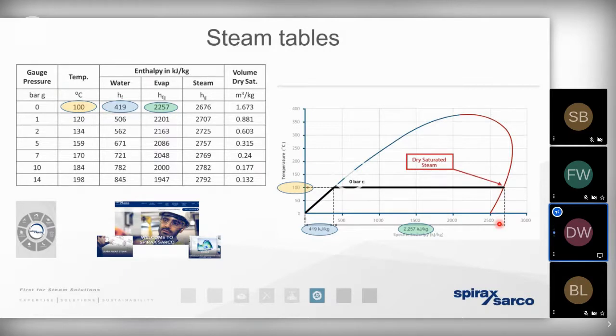So you remember from previous presentations, we've highlighted how wet steam is the biggest enemy of a well-designed steam distribution network. Simply put, the wetter the steam, the greater the heat loss, the greater the condensate load is going to be on the distribution pipework. And the greater the heat loss, the greater the inefficiency. If we've got more condensate in the pipework, we've got to install a greater number of steam traps to drain that condensate away. That's going to be at some capital cost. It also means we're at greater risk of erosion, corrosion, and water hammer. And because the steam's wet, it means we're at a greater risk of that moisture contaminating an atmosphere. And it also means that that steam is going to have less energy contained within it.